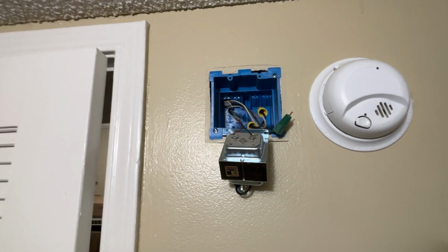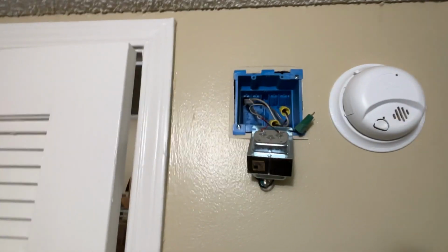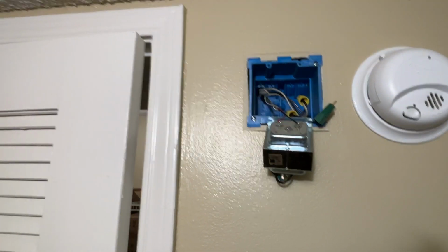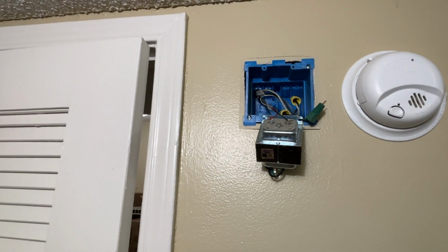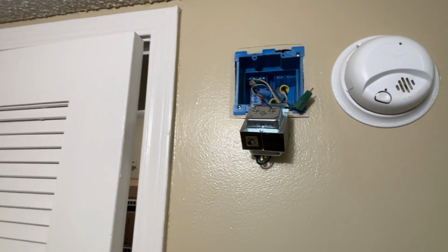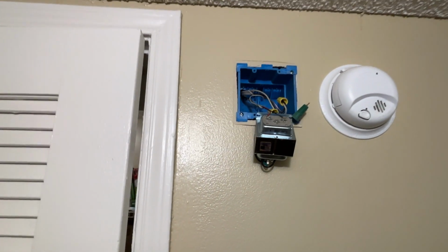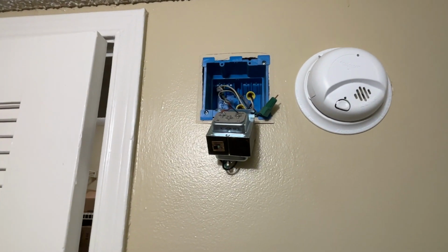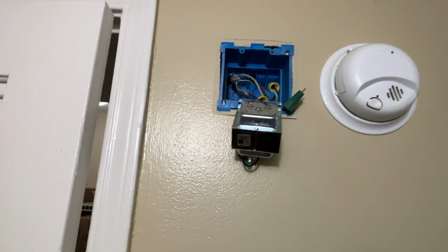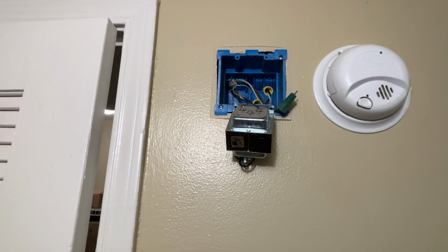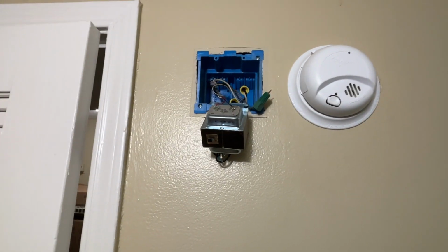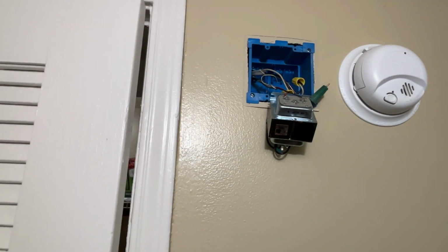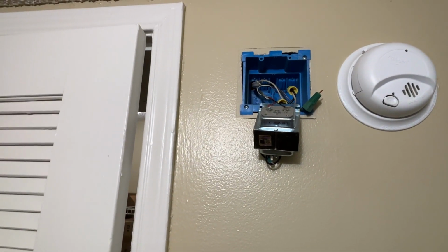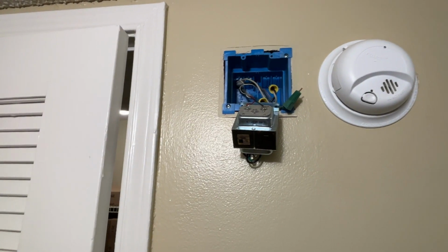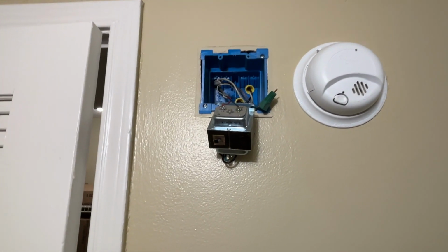If we have power in and out of the transformer, in and out of the switch, and we have power going to the strobe right at the wire nut connection, but our siren and strobe is not sounding or flashing or lighting up, then we know we need to replace that siren and strobe. If the siren's activating and the light is not lighting up, then we can see if we can replace that bulb. If the bulb is integrated, we need to replace the whole siren and strobe. If your light is lighting up but the siren is not sounding and you verified you have power, then you need to replace your siren and strobe as well.